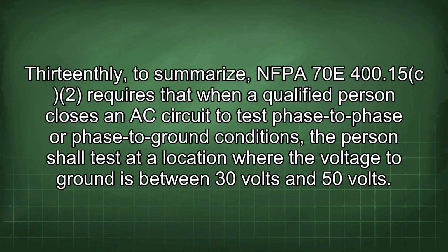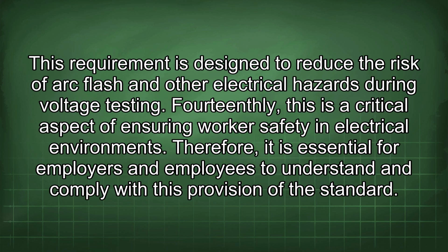13thly, to summarize, NFPA 70E 400.15 requires that when a qualified person closes an AC circuit to test phase-to-phase or phase-to-ground conditions, the person shall test at a location where the voltage to ground is between 30 volts and 50 volts. This requirement is designed to reduce the risk of arc flash and other electrical hazards during voltage testing. 14thly, this is a critical aspect of ensuring worker safety in electrical environments. Therefore, it is essential for employers and employees to understand and comply with this provision of the standard.